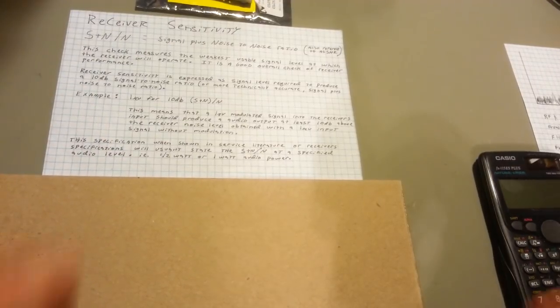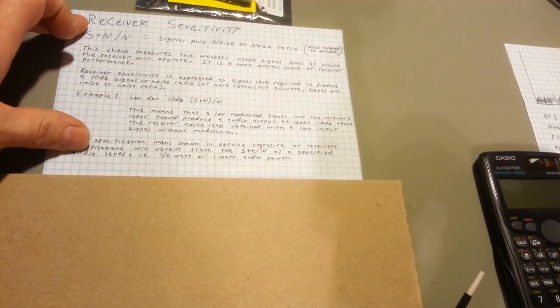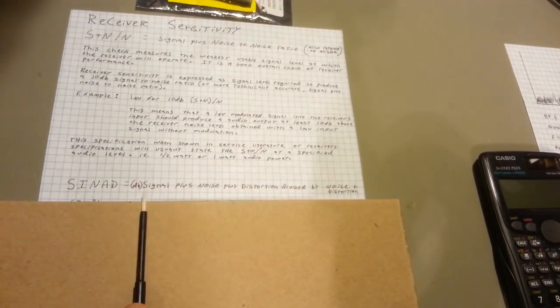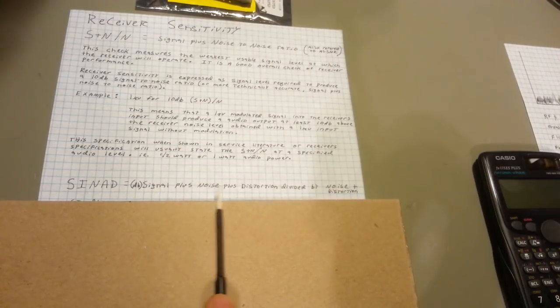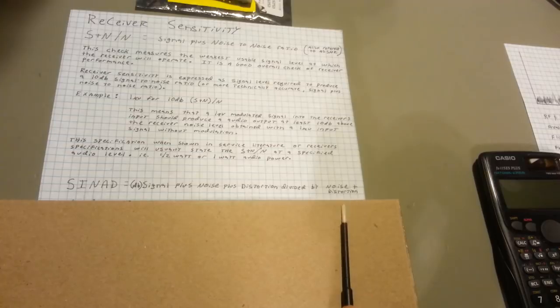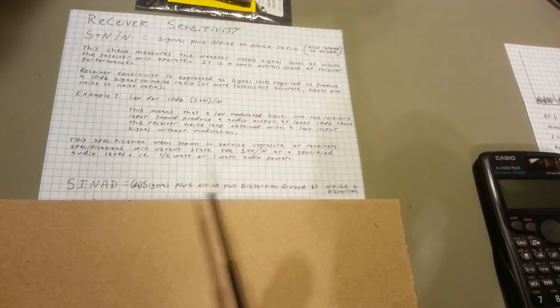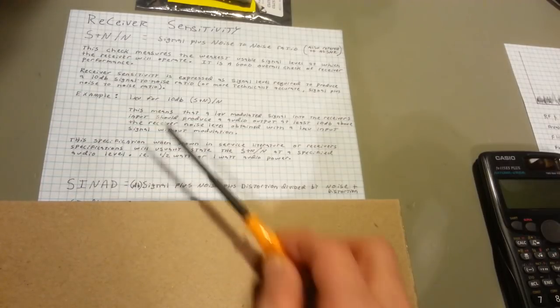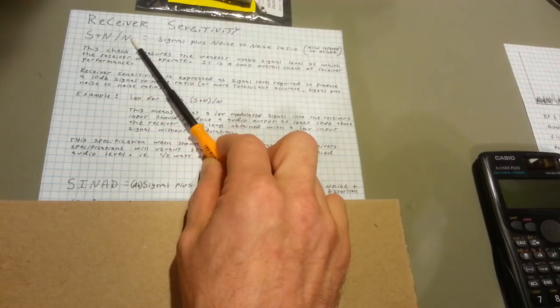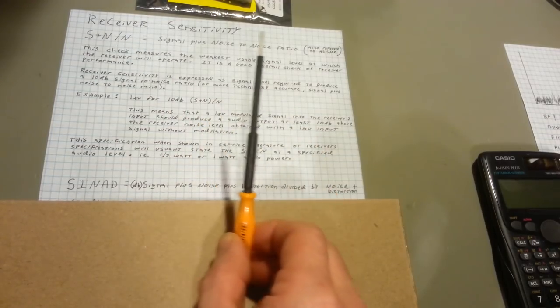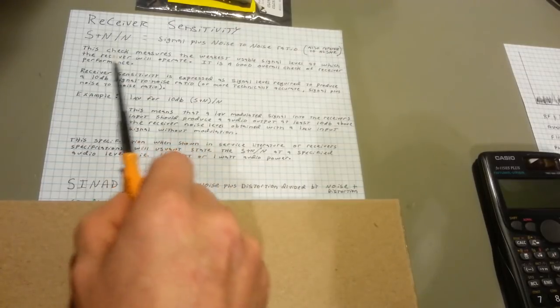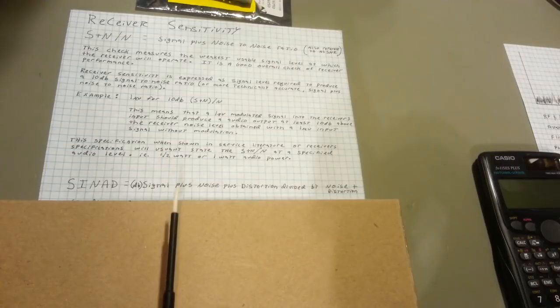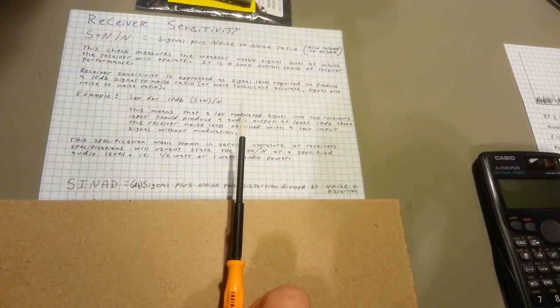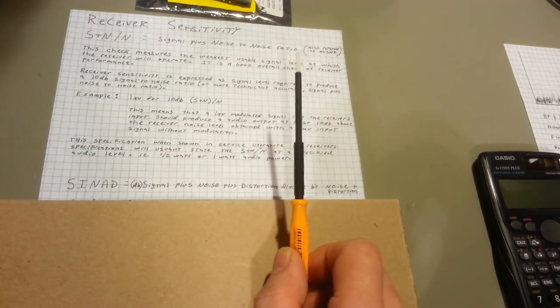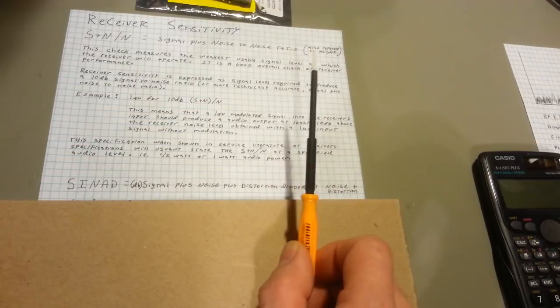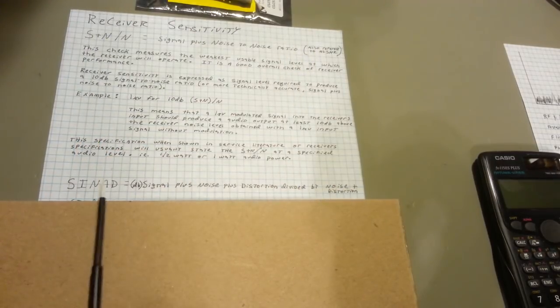Another common one, and it has not been around anywhere close to as long as signal plus noise to noise ratio, is SINAD. So, SINAD, and this is always measured in dB, is the signal plus noise plus distortion divided by noise and distortion. I prefer this one because this takes into account distortion, where this one doesn't. So if your audio amplifier in your radio is causing possibly the frequency to shift slightly, this one is not going to account for that. If you inject a pure 1000 hertz modulated tone into a radio, and the audio amplifier circuit, or any circuit in a radio, is causing audio distortion, this measurement won't account for that. This does.